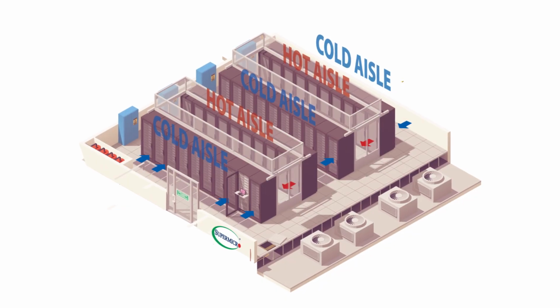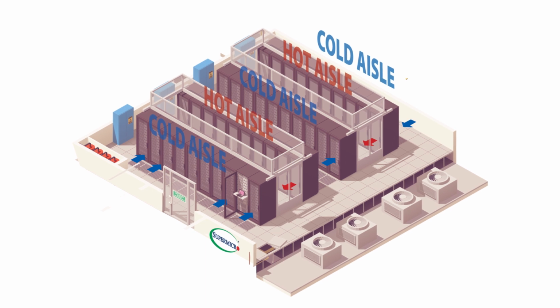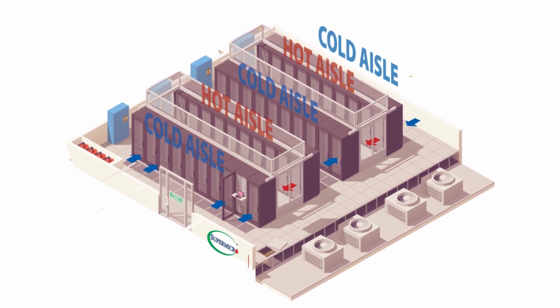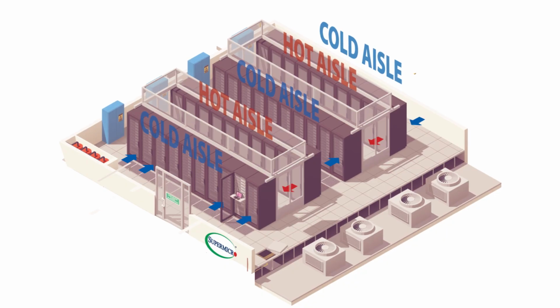Let me explain the difference briefly. Hot aisle and cold aisle containment are similar in that you have a box surrounding two or multiple rows of servers. In a cold aisle setup, air is pulled in through the containment and pushed out through the back of the servers. In a hot aisle environment, air is pulled through the front in the data center and into the containment in the middle. The difference is that with hot aisle, the air is pulled through ductwork at the top and then into the air conditioning system, where it's replenished and cooled.